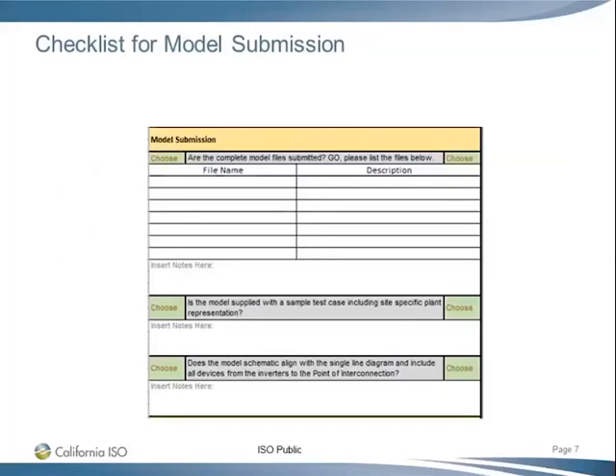So this is the checklist for the model submission. We ask you to tell us which files you are submitting and give a brief description of each file. Then you have to self-check and confirm that the test case you submit includes site-specific plant representation. That means you don't just take the model from the manufacturer and submit it to us. You need to take the model from the manufacturer, customize it to your project, make everything site-specific, then provide it to us. And then answer the other questions, such as whether the model aligns with the single line diagram. Whatever is shown on your single line diagram should be reflected in the EMT model, from the inverters or generators all the way to the point of interconnection. So you need to make sure you can answer yes to those questions before you make a submission.